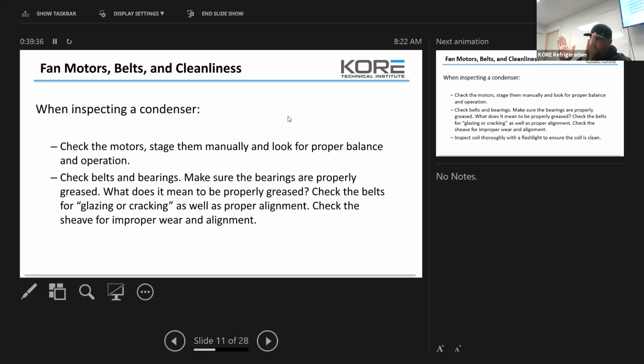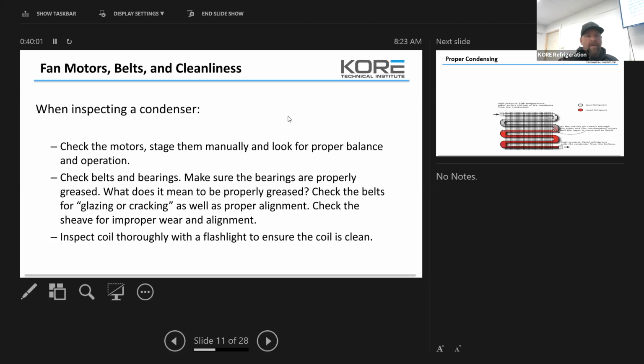Make sure that sheave is nice and V'd as well, and then it's adjusted properly. The alignment should be straight. So the sheave surface should be a nice V shape. If it's U'd out, where it's worn out because it's been resting to one side or the other and it's worn away on that metal with friction, it's time to change that sheave. So we need to make those suggestions when we're finding that.